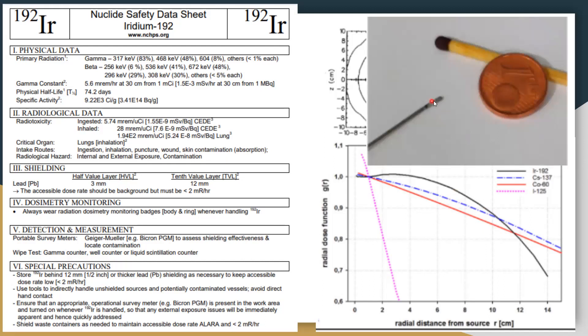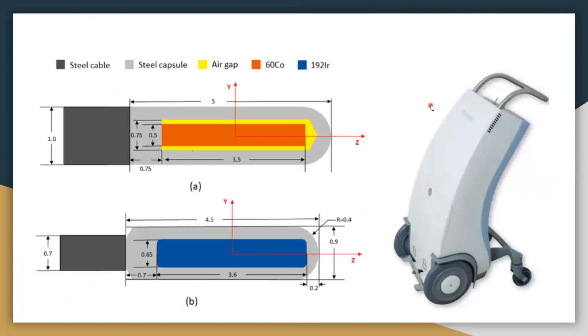This is a typical source size. These are the things for comparison. The iridium source is popular because of high specific activity, which allows us to make a very small source size. This is the difference between the iridium source and the cobalt-60 source. You can see the difference in the size. Nowadays, cobalt-60 is also in the clinics because of higher half-life, so it's quite economical. But shielding requirement increases.